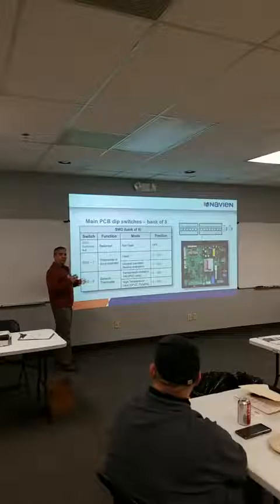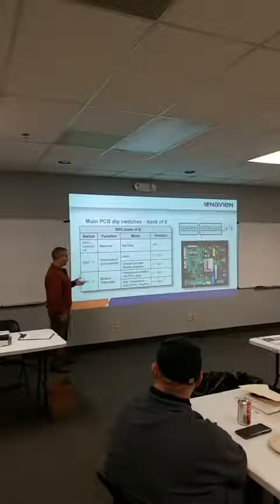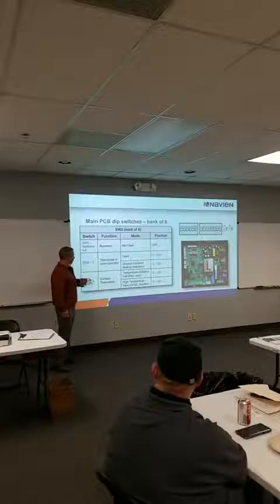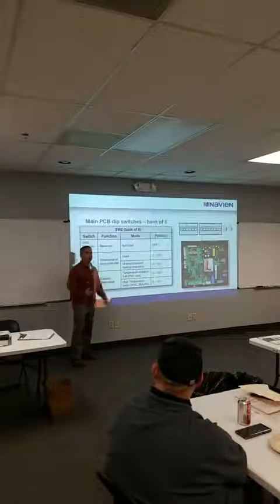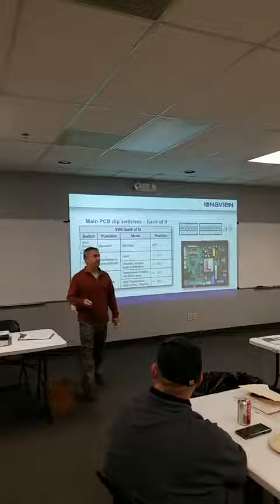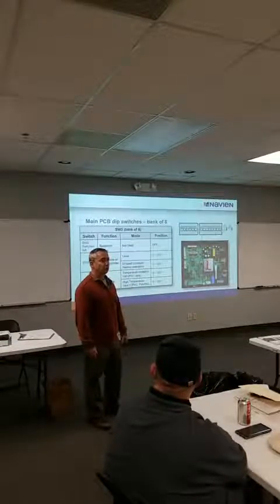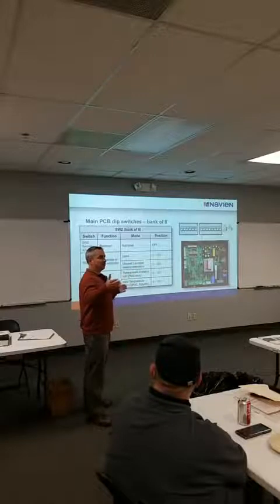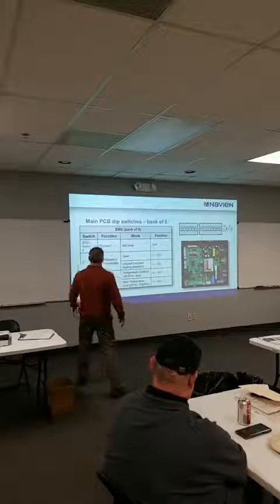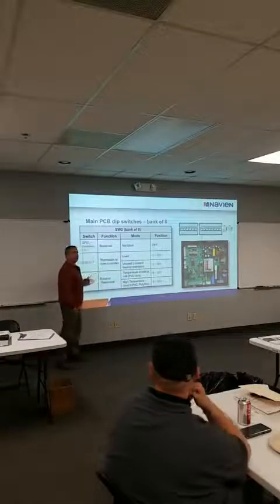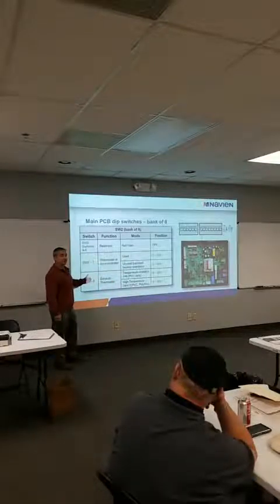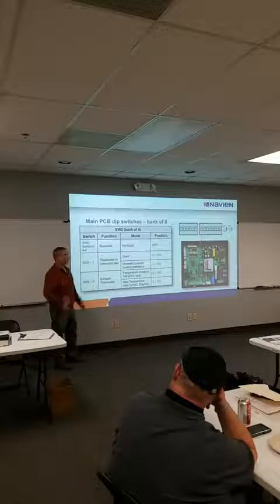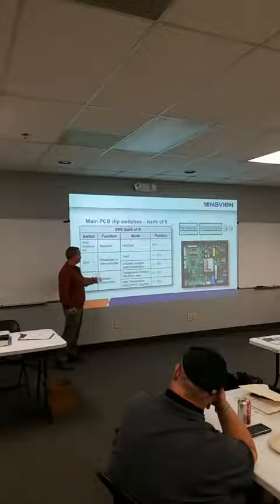If you have return water temperatures over 150 degrees, your flue temperatures are gonna come up, of course. So you have to put number 8 on, and you gotta change our flue material from Sched 40 PVC to like Sched 80 CPVC or Polypro, something like that, at least for 18 to 24 inches, and then you can go to Sched 40 PVC if you wanted to. But if you don't hit this switch and you have a 180 degree supply system, you're never gonna get to that temperature because we're limiting the exhaust temperature to 149.